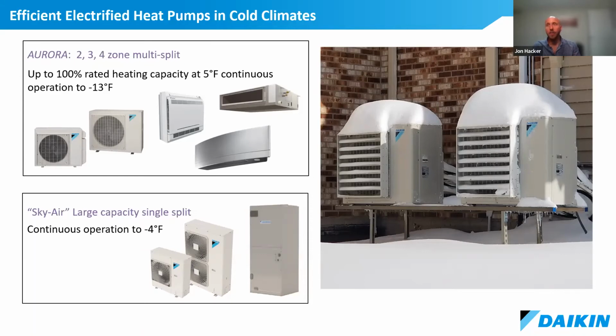I'd suggest the Sky Air is really used when there's existing ductwork in the home for retrofit application, or in a new construction when there's going to be central ducting available, or the Aurora is used really for a retrofit. Maybe you have a boiler in place, no central ducting. It's a great solution for that. If you need longer line lengths for multifamily application, at that point, you might want to start thinking about the VRV line of products, either single phase electric or triple phase electric as well.